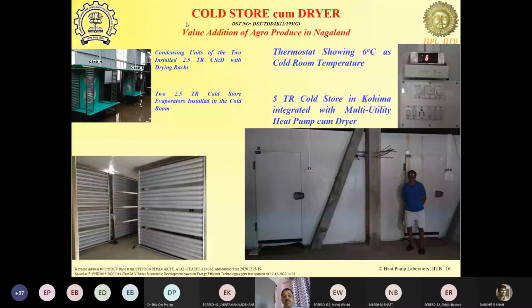Then we have used heat pumps for cold store operation, and to improve the economic sustainability of the cold store, we are recovering the condenser heat and using it for drying of agro produce. So this is the drying side of the agro. We would put the trays here and cover this up, and then the condenser air will help us dry the produce in this case. And the indoor was maintained at 6 degrees centigrade here. And this was set up in Nagaland, and we had ice bank tanks deployed as the evaporator of this. So even if the electricity is not available for up to 4 hours, you'll continue to get the cooling effect without much difficulty.